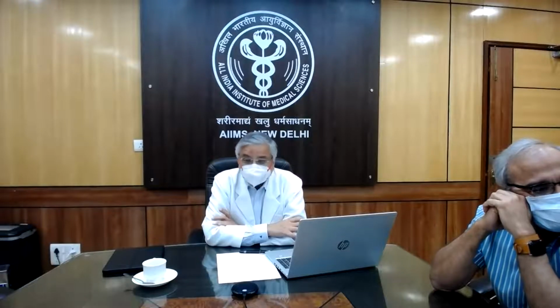The first issue is, I think, what Dr. Vimi very importantly said: it's important to understand what is high flow and what is low flow oxygen. It's not related to the flow rate. It's not that if you have a 10-liter oxygen, it's a high flow oxygen. The high flow oxygen system is one which meets the entire inspiratory demand of the patient. So even a Venturi mask is a high flow system, although you may be giving it at a lower flow rate as compared to what is a low flow system.